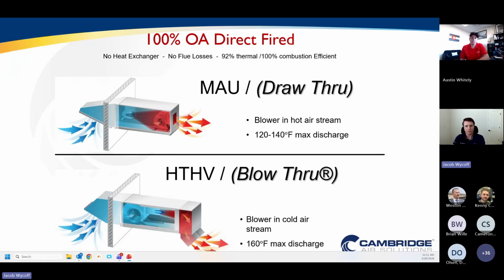Whereas whenever you look at draw-through style equipment, that blower's in the hot air stream, which limits your discharge temperature anywhere from 120 to 140 degrees at the absolute max. And really, if you tried to operate the unit consistently at 140 degrees, you're going to see very short lifespans out of your blower components, like your belts and your bearings and your motors, because they're not made to be subjected consistently to those very high temperatures. The blow-through style unit allows us to have that high discharge temperature, keeping those blower components in the cold air stream, allowing them to last with longevity, while still providing large levels of heat to the space.